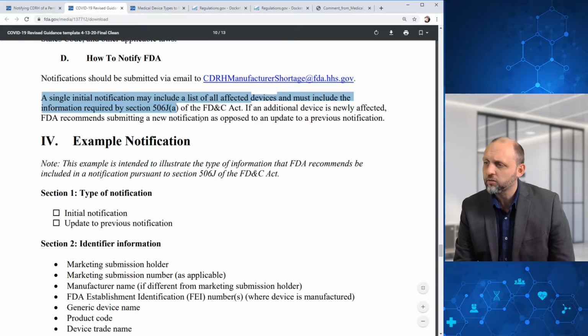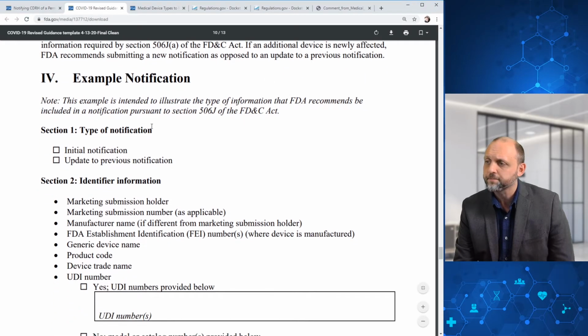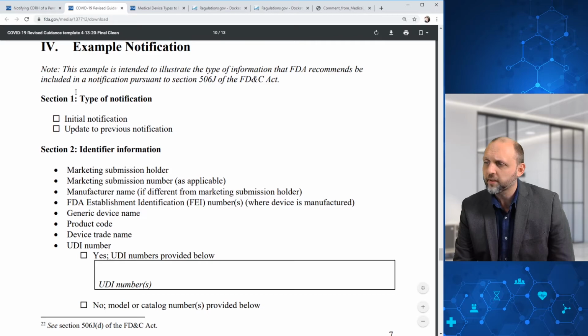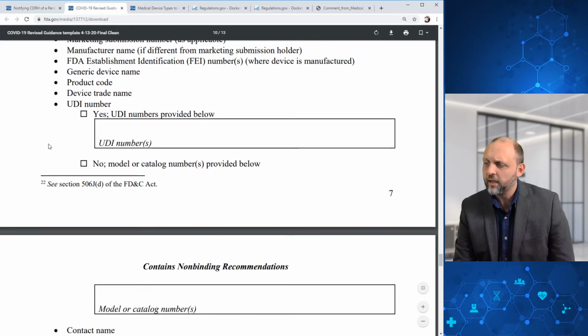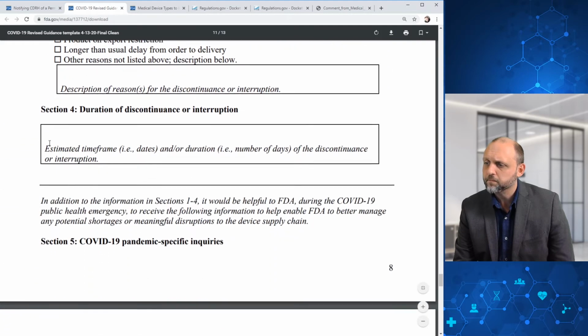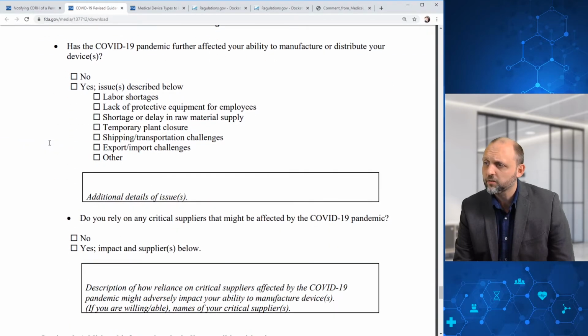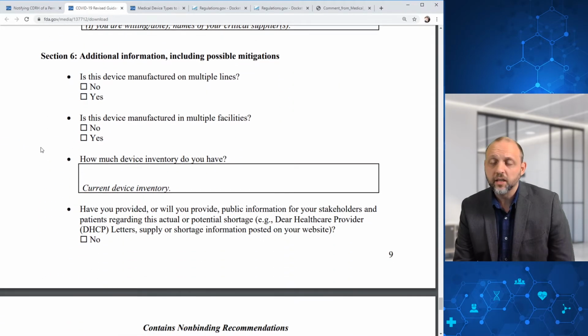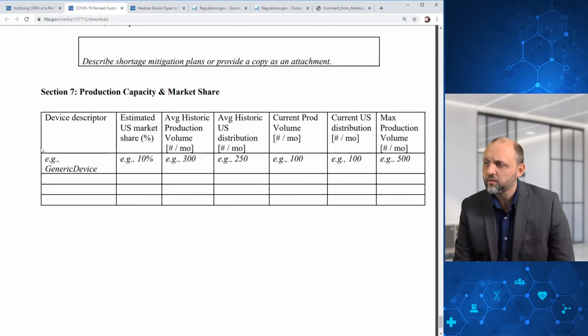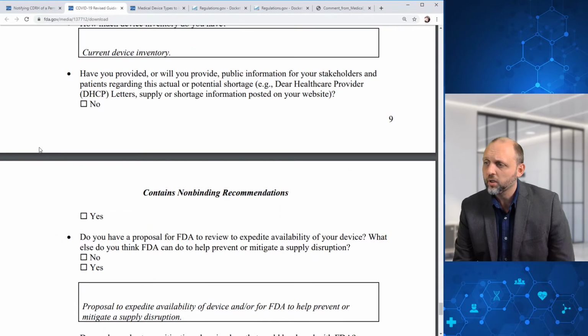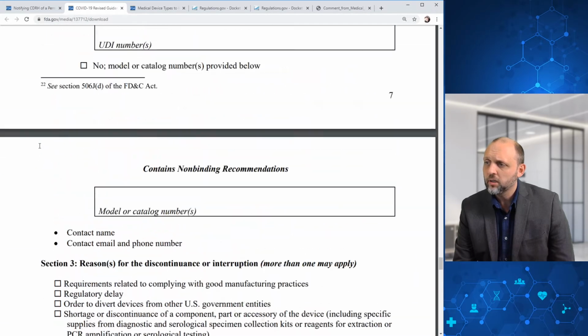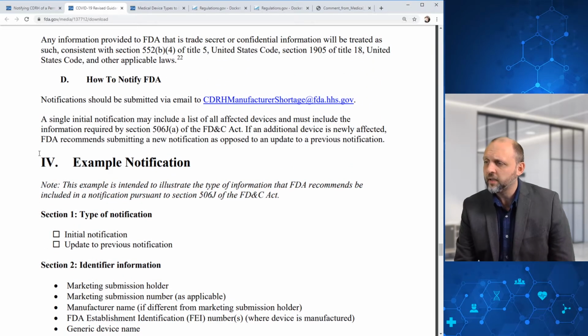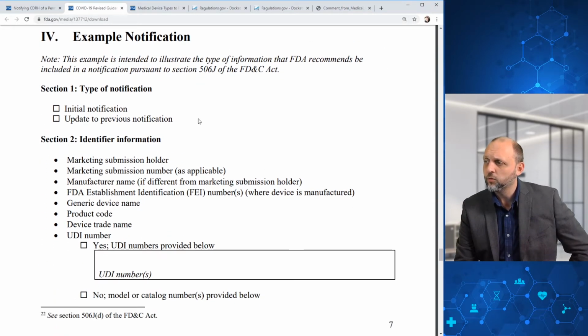If an additional device is newly affected, FDA recommends submitting a new notification as opposed to an update to a previous notification. And here's an example notification with the detail that FDA would like to see. And it's fairly comprehensive. And again, as FDA said, if you don't have all of this information available, share what you do as an initial submission and then update it as you move forward.